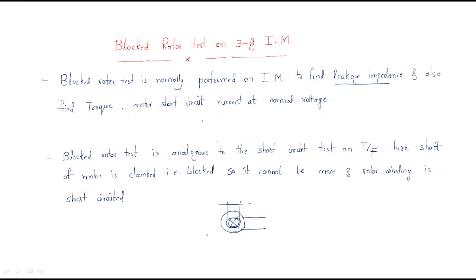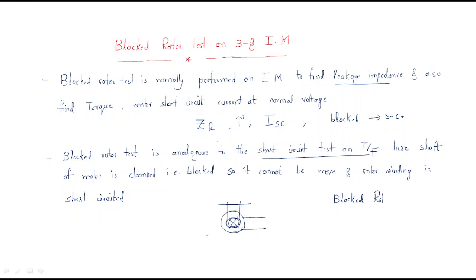The block rotor test is used to find the leakage impedance ZL, torque, and also the motor short circuit current. It is also called the short circuit test — both are the same. The block rotor test on a three-phase induction motor is analogous to the short circuit test on a transformer.